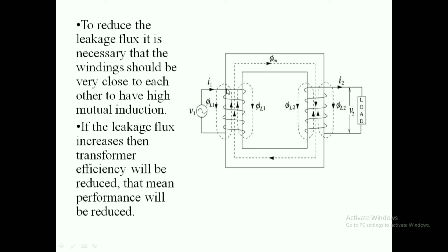Leakage flux means, when the primary winding is connected with the supply, then a current, here I1, flows through the primary winding and it generates flux which flows through the magnetic core and links the secondary winding. Suppose it generates 100 units of flux, but our motto is to flow the 100 units through this magnetic core, but generally 100% does not flow through this magnetic core. Some losses are here also, and these are phi L1 and phi L2 which don't flow through the magnetic core. These are called leakage flux.